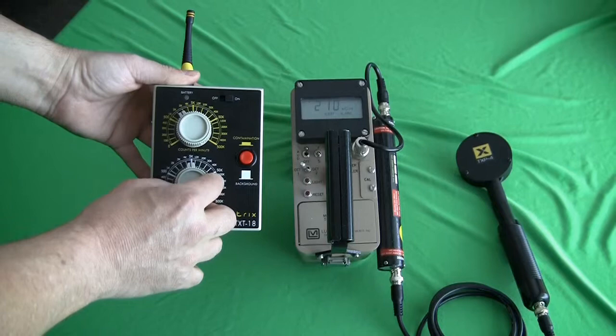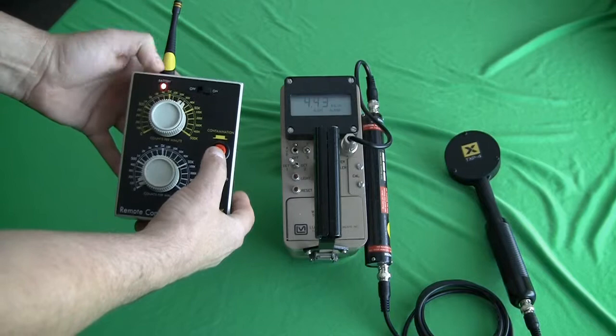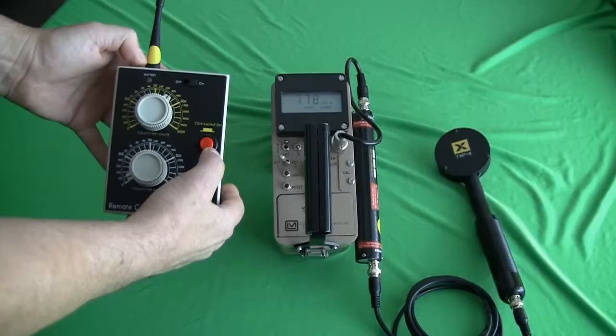In certain instances, it's desirable to use the bottom control to set a background reading and the top control for a contamination reading, and simply switch between the two using a push button.